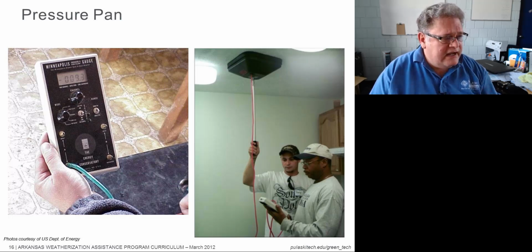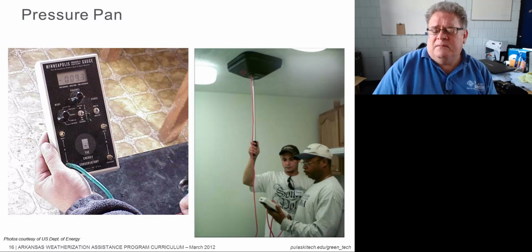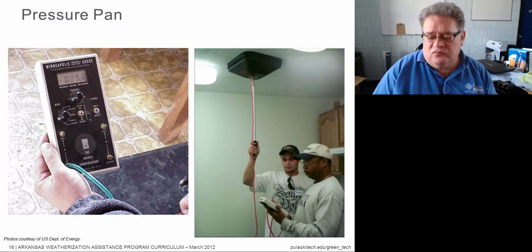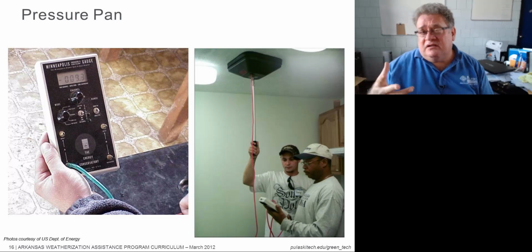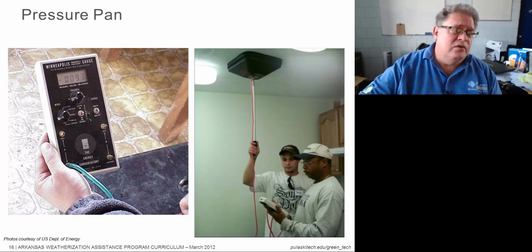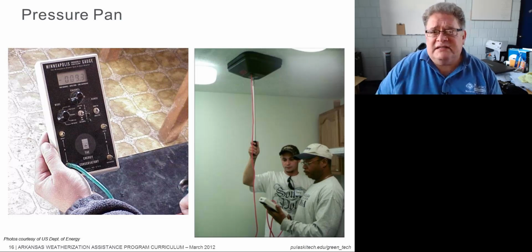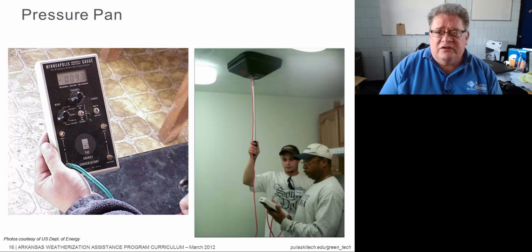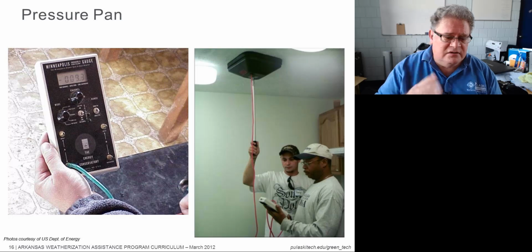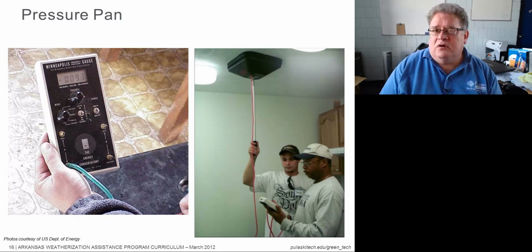Okay. Now, what do we use manometers for? Well, pressure pan tests are probably one of the most often run tests. And we like them because it's very quick feedback on duct sealing. If we seal a run of ducts, we can put a blower door up and go run pressure pan and see how we've done. Pressure pan is also really good on helping to locate the area that we need to pay attention to as far as duct leakage goes on the supply side. If we're getting a big number, we know we're getting closer. If the number keeps getting larger, we know we're probably getting closer to it. That saves work. We can start right there where the big numbers are, spend our money on the big numbers, bring those numbers back down to something reasonable, and then move on to another project if they get in the right neighborhood.